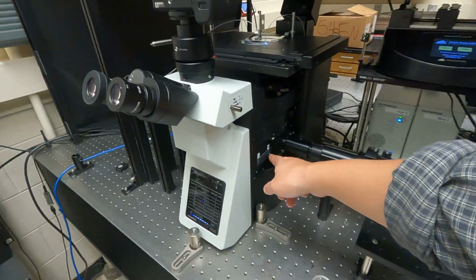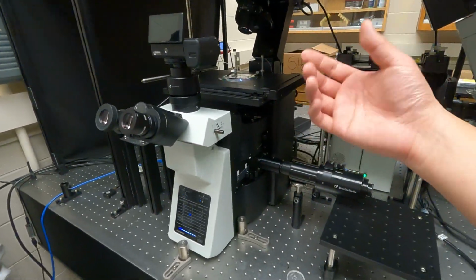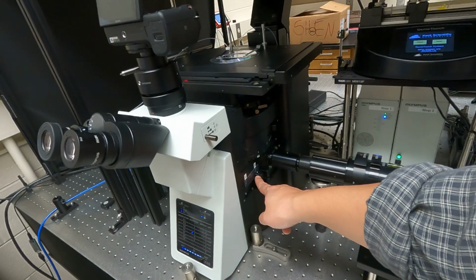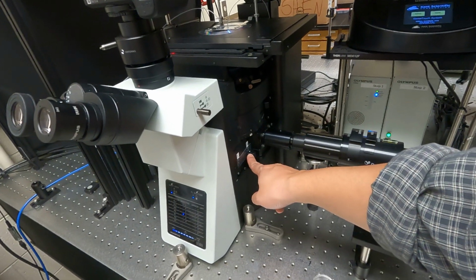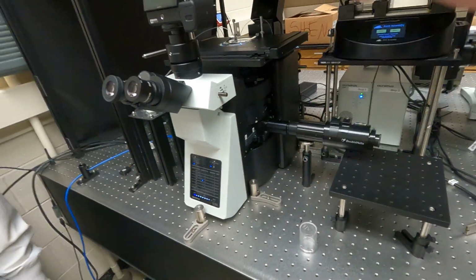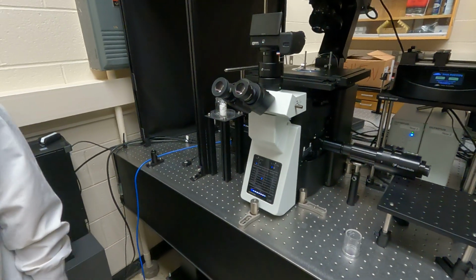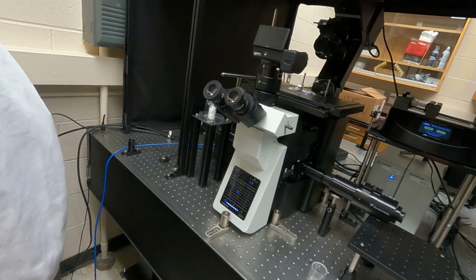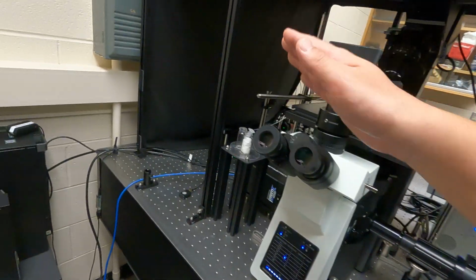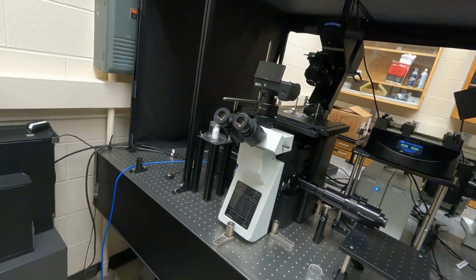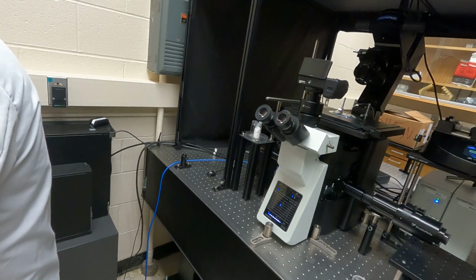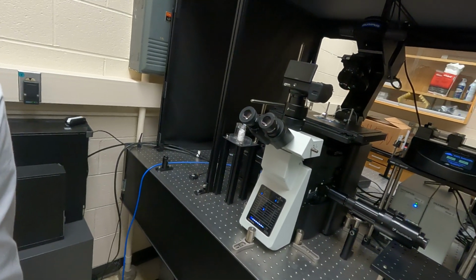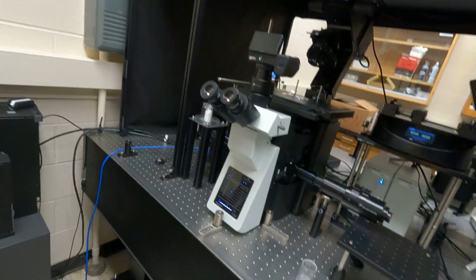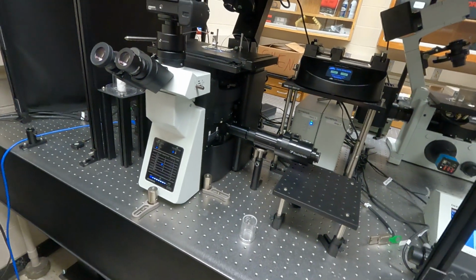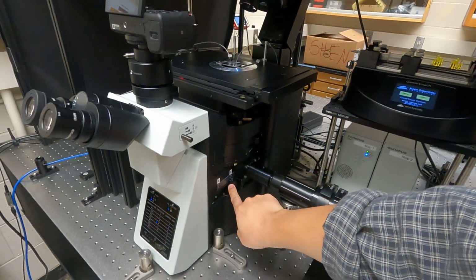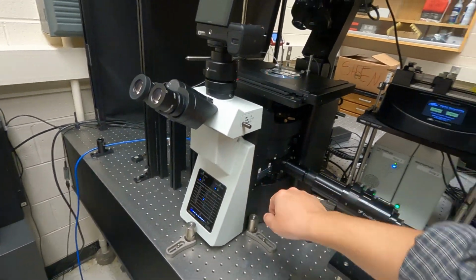So switching this selector to the right side is effectively shutting down the light that gets into the camera. So before you finish all of the preparation work, you would want to put this selector on the right side port so that light will not get into the ultra-sensitive camera and potentially saturate the entire detection. Because this is so sensitive, the ambient light in this room could easily saturate the whole thing and potentially damage the sensor there. So while it is not in use, it is always good practice to move the selector to the right side.